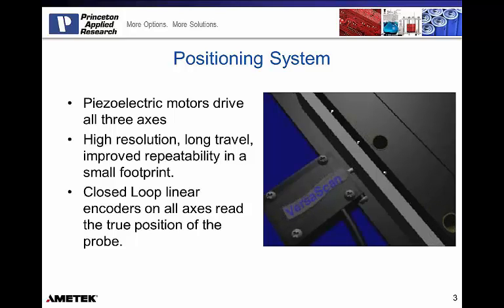There are two popular ways to create movement by the positioning system. This can either be by stepper motors or piezoelectric motors. The VersaScan system is comprised solely of piezoelectric motors to drive the three axes. These piezoelectric motors provide high resolution, long travel, and improved repeatability, all within a small footprint. This is a closed-loop positioning system. A closed-loop positioning system means that there's a feedback mechanism that moves the probe to the requested position. This is in comparison to an open-loop positioning system that requires a factory calibration and relies on that factory calibration to estimate the positioning of the probe. A closed-loop positioning system gives you that feedback and ensures the probe is in the exact position that the user has requested.